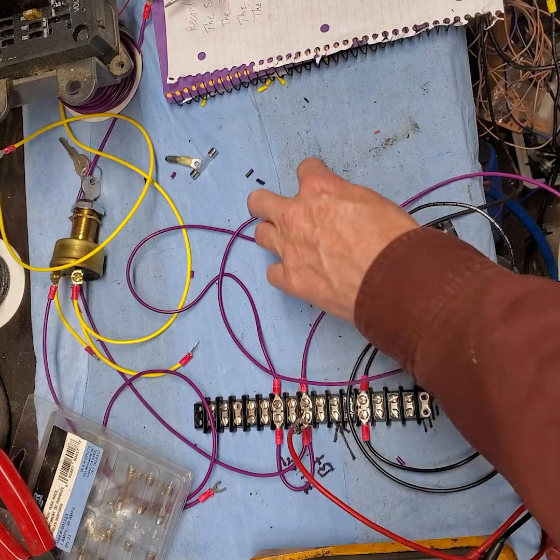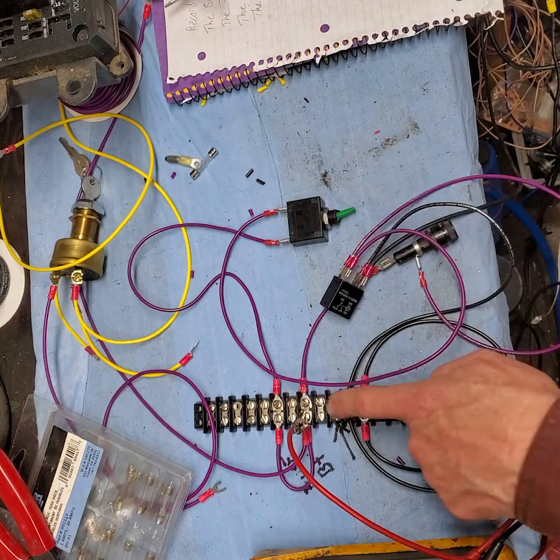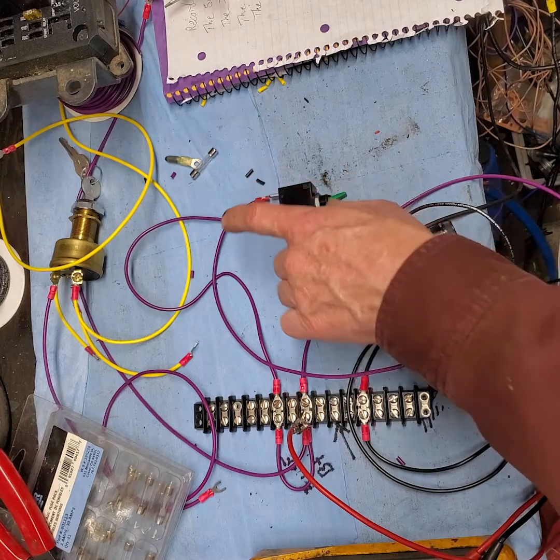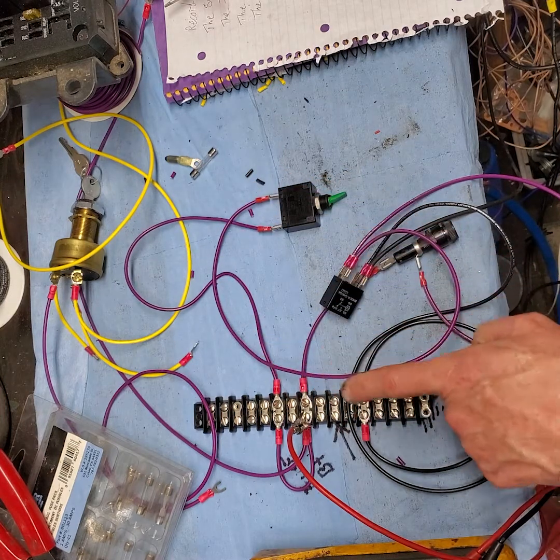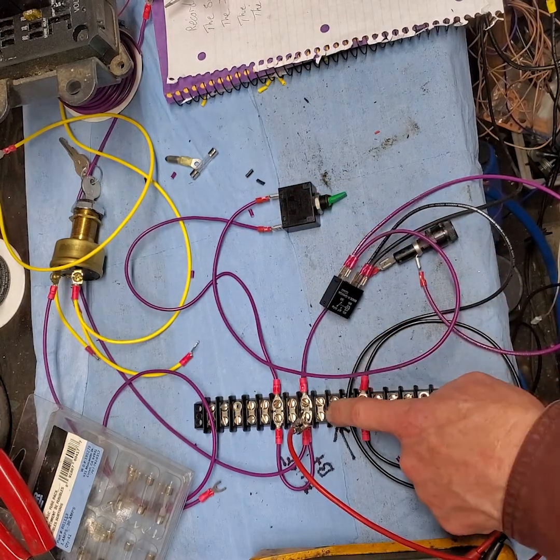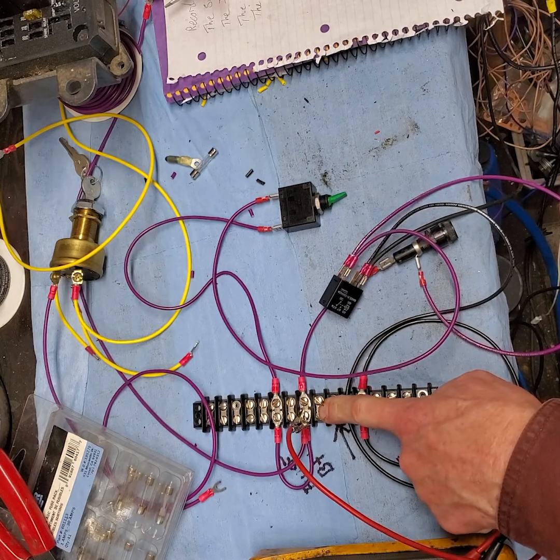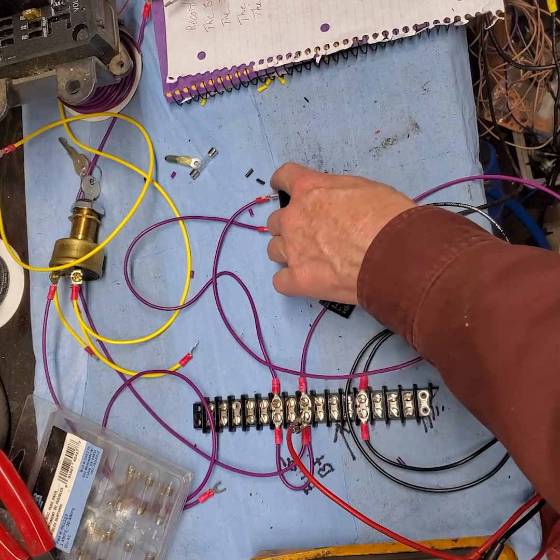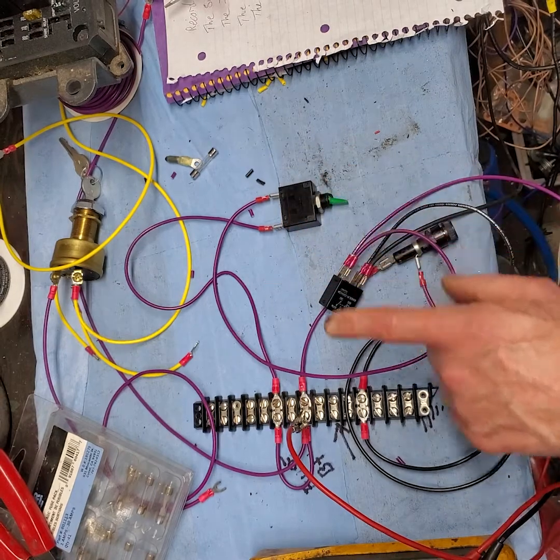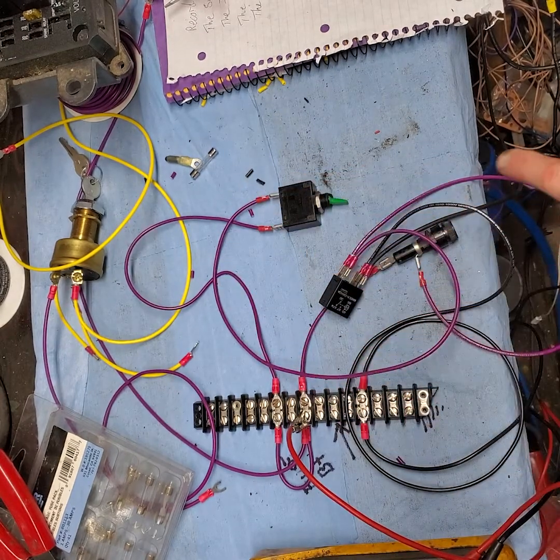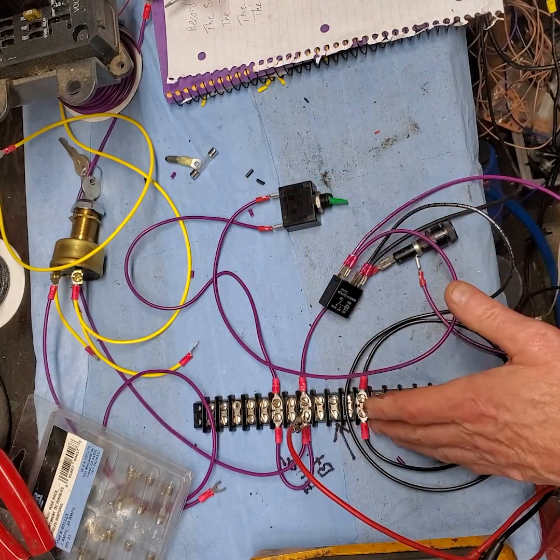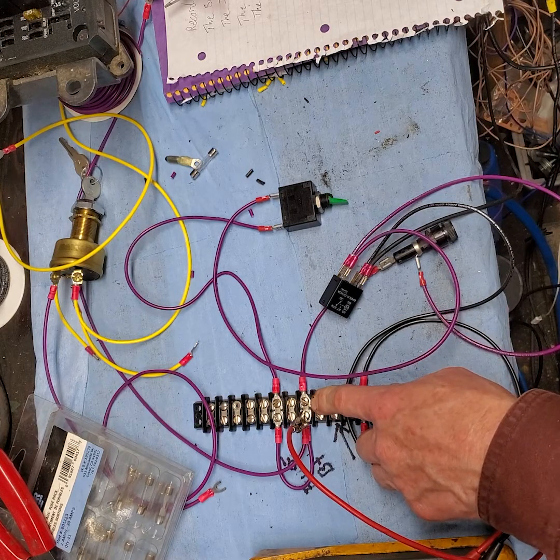Because the voltage, I've thrown this switch. If I shut the switch off, there's no continuity. I need to energize the circuit every time you're going to do a voltage drop. Here's the rule. Write this in your notebook. Energize the circuit. I have to allow the current to flow wherever it can, and wherever it stops, I'm going to read it where it stops.